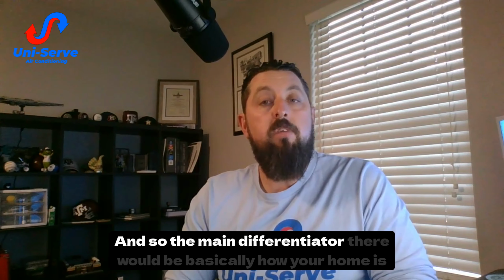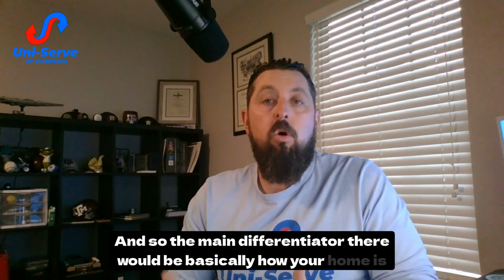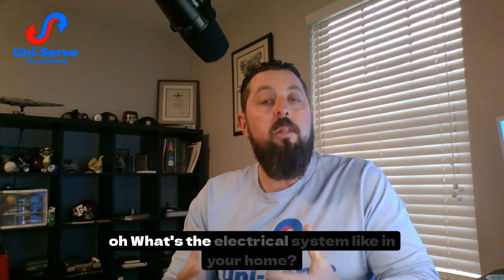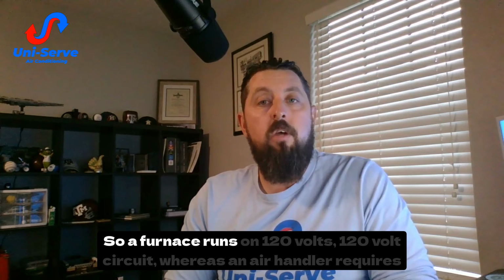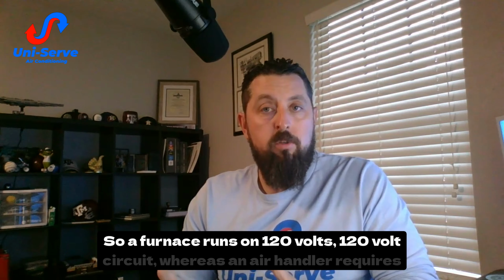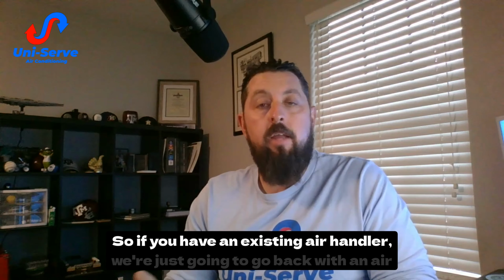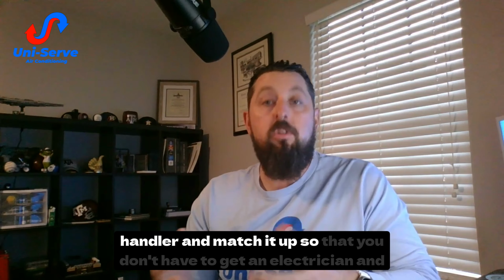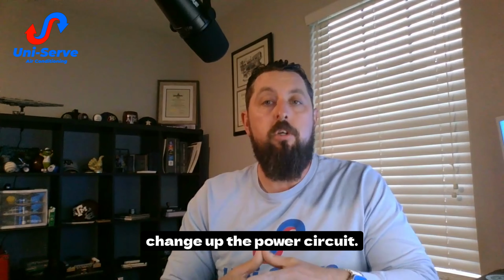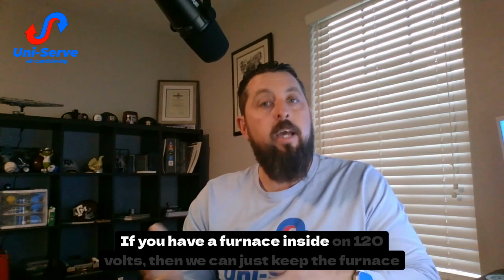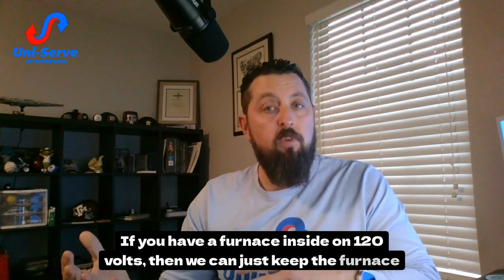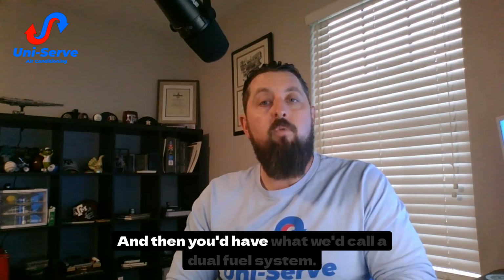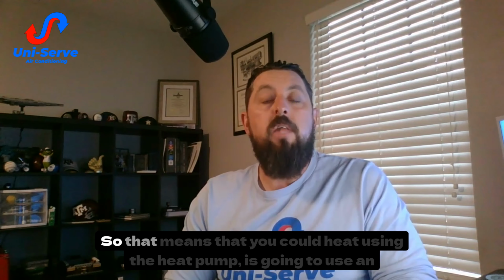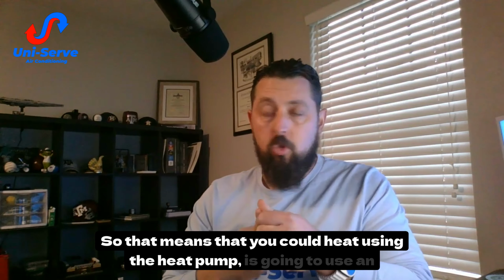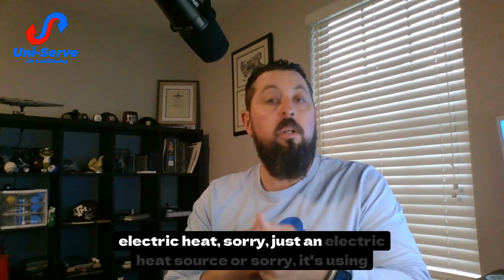And so the main differentiator there would be basically how your home is designed. What's the electrical system like in your home? So a furnace runs on a 120 volt circuit, whereas an air handler requires a 230 volt circuit. So if you have an existing air handler, we're just going to go back with an air handler and match it up so that you don't have to get an electrician and change up the power circuit. If you have a furnace inside on 120 volts, then we can just keep the furnace and put a heat pump outside, and then you'd have what we'd call a dual fuel system.